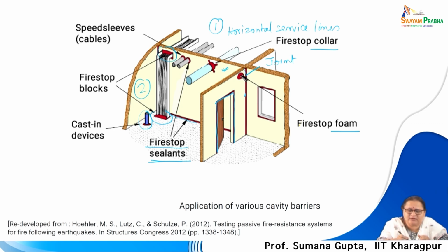So, it is not only the pipelines and services, but even the in-between wall, which may be of fire grade, but because of that gap between the two, it is a temporary partition wall, maybe a temporary wall. So, all areas are checked, or all leaks are proofed, so that no fire or smoke can move from one space to the other.